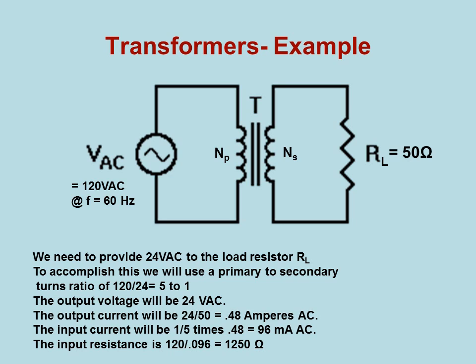Here is an example. We want to make 24 volts AC, probably to run some things at a lower voltage. A lot of control mechanisms are run at 24 volts because it's a relatively safe voltage. To accomplish this yields a primary to secondary turns ratio of 120 over 24, which is 5 to 1. The output would then be 24 volts AC. The output current will be 24 divided by 50, or 0.48 amperes AC. And the input current will be 1 over 5 times 0.48, or 96 milliamps AC.